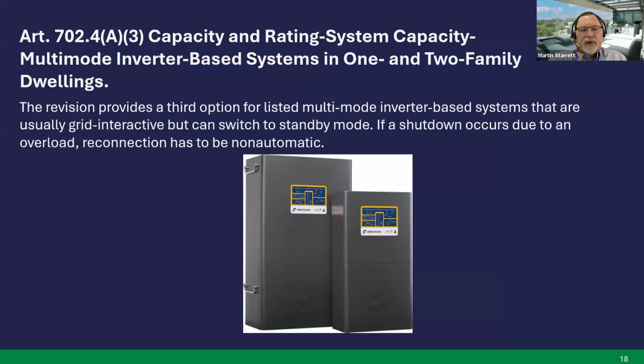In Article 702.4A3, capacity and rating, system capacity, multi-mode inverter based systems in 1 and 2 family dwellings. This revision provides a third option for listed multi-mode inverter-based systems that are usually grid interactive but can switch to standby mode. If a shutdown does occur due to an overload, the reconnection has to be non-automatic. Next slide.